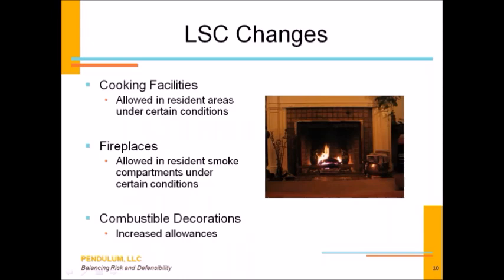When it comes to that home-like environment, there are new requirements that allow you to have cooking facilities with some limited use within your smoke compartments. You're allowed to have a single open-sourced cooking area within a smoke compartment that serves no more than 30 residents, providing that it's fully sprinklered and the cooking device, including a residential quality stovetop or range, can be within those areas, providing that they're only used for food preparation purposes.